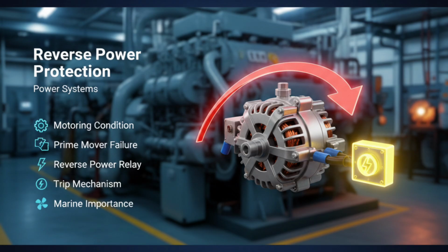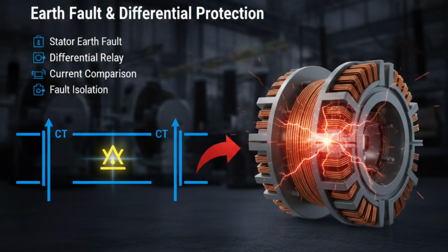Reverse power relays detect power flow direction. If reverse power exceeds a preset percentage, typically 5-10% of rated power, the breaker trips automatically. In marine systems, this protection prevents engine damage and reduces blackout risks. Earth fault or differential protection. This slide shows stator windings with a highlighted earth fault zone.